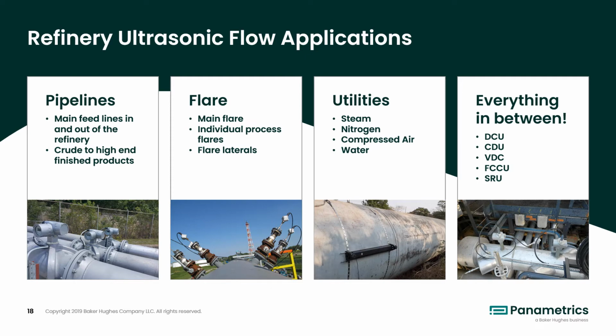For flare lines, ultrasonic flow meters such as our GF868 and XGF868i ultrasonic flow meters are almost exclusively used for the main refinery flares, local unit flares, and flare laterals due to the versatility they provide for monitoring extreme low flow rates and then extreme high flow rates above 300 feet per second in upset conditions. Along with extreme flow rates, the ultrasonic flow meter handles changing stream compositions, including high levels of carbon dioxide or even hydrogen. Utility measurements, including steam, nitrogen, compressed air, and water, use ultrasonic flow meters.